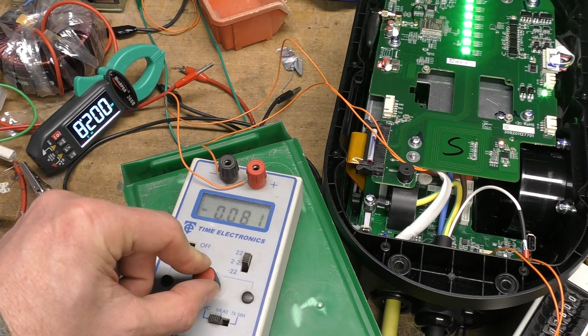This is important because cars have rectifiers in the charger, so it is plausible that you can get earth leakage faults which have a significant DC component, and that can be a problem because if you've got an upstream AC RCD which isn't designed to cope with DC, it can actually blind it to real faults because it saturates the current sensing transformer. Yeah, so it's 5 milliamps, which is fine. Flip the polarity. Turn the car on. Again, 4.5 milliamps, which is absolutely fine. 6 milliamps is generally regarded as the maximum limit that it should have.